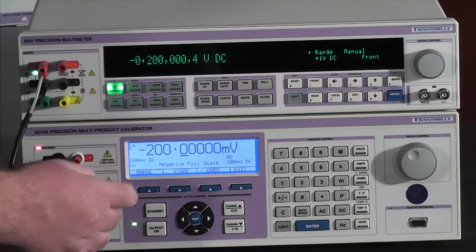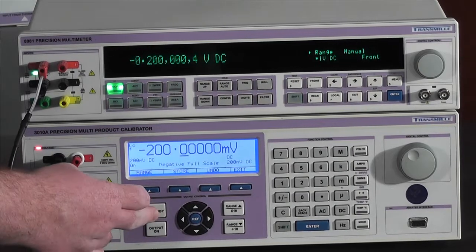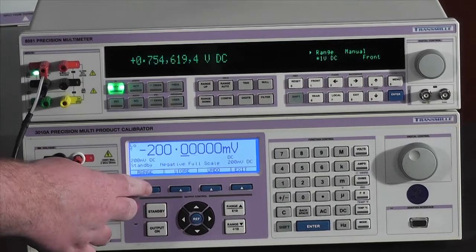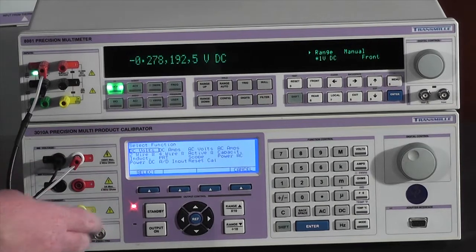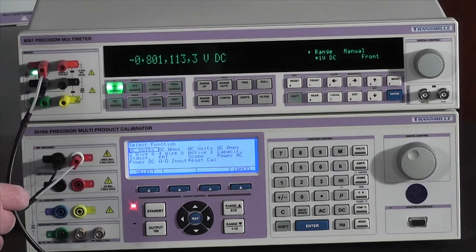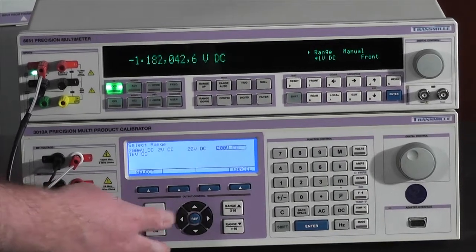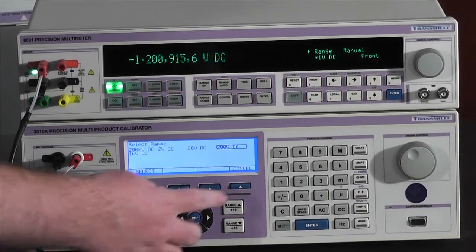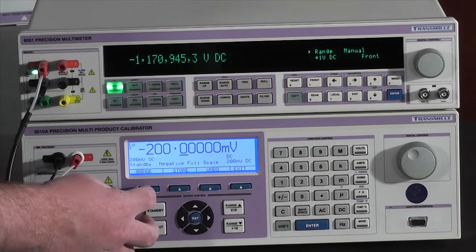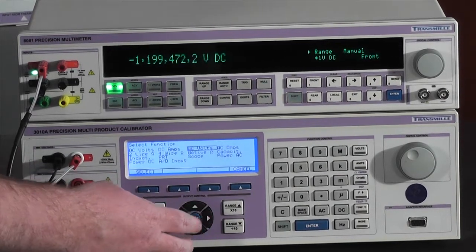Now that we have adjusted the 200 millivolt range, we can press standby and press the range key. This will then take us back to the calibration menu, where we can either further proceed with more adjustments in the DC voltage or adjust other ranges.